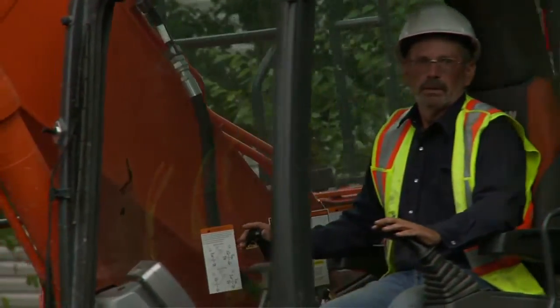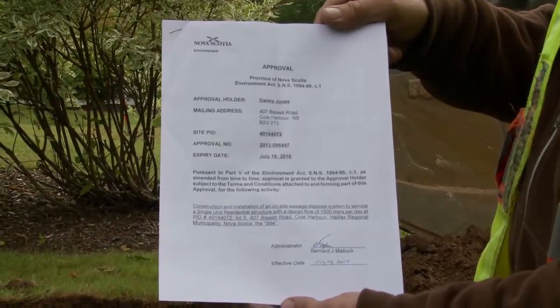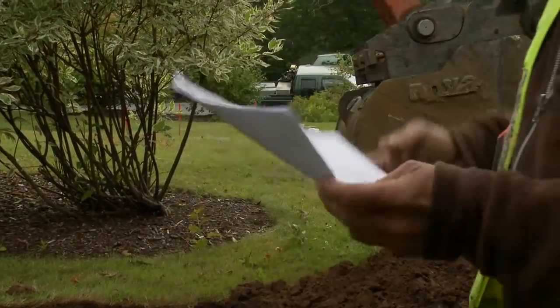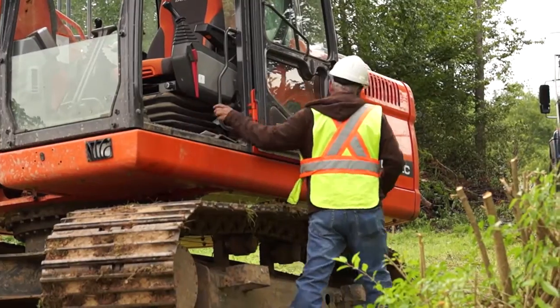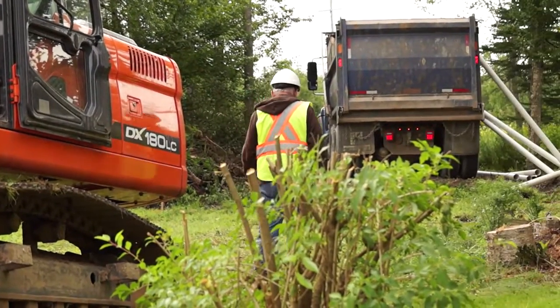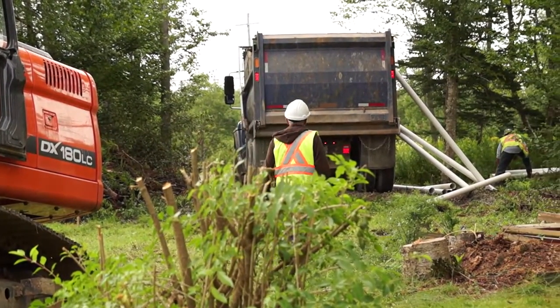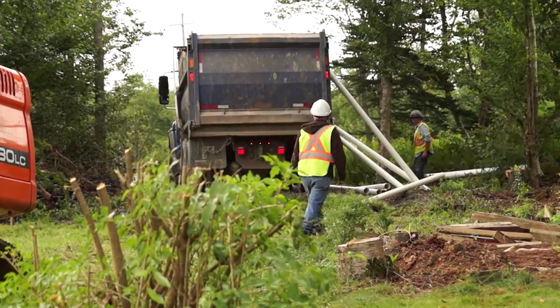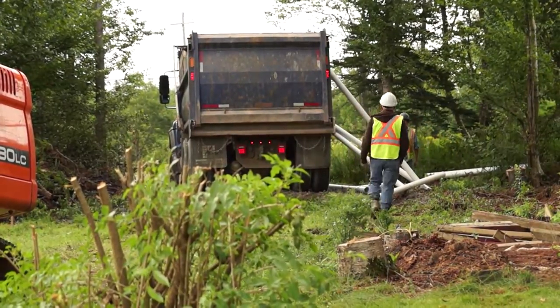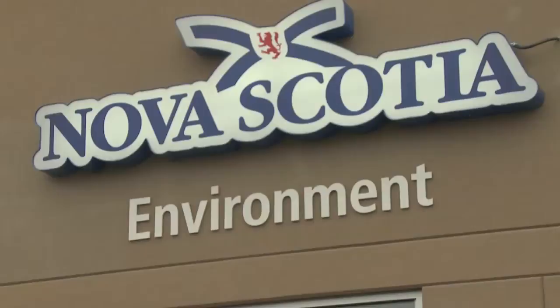The installer obtains a copy of the on-site sewage approval and reviews the plan for the property. The installer contacts the qualified person and advises that he is installing the system and of the date that he will have the system constructed and left open ready for inspection. The qualified person will give Nova Scotia Environment 3 days notice of this date.